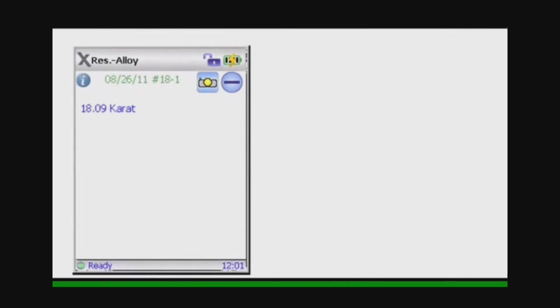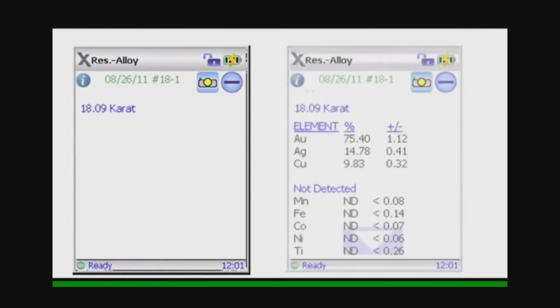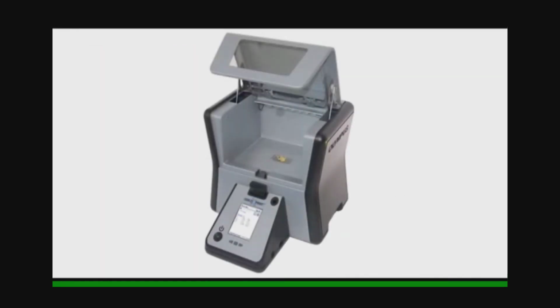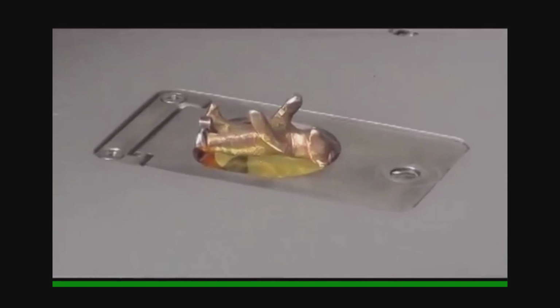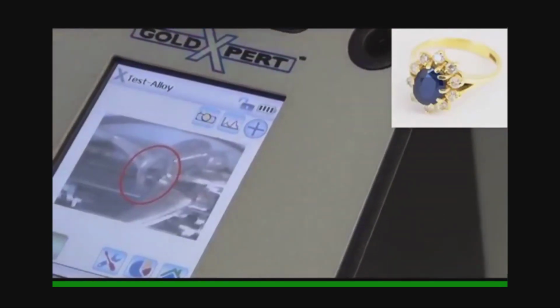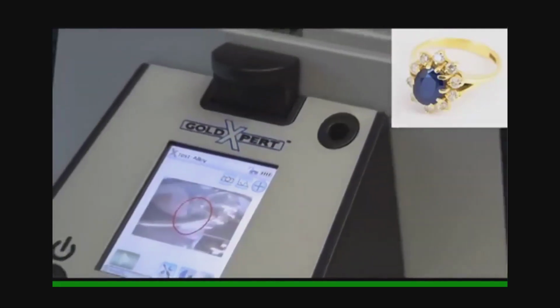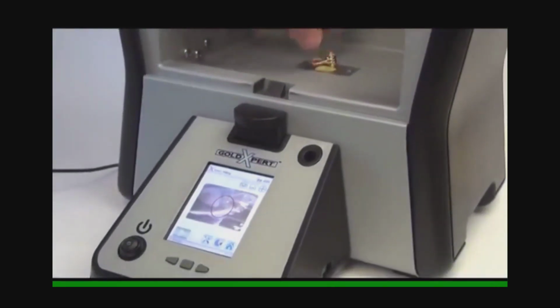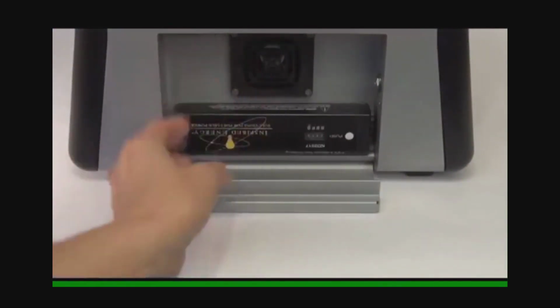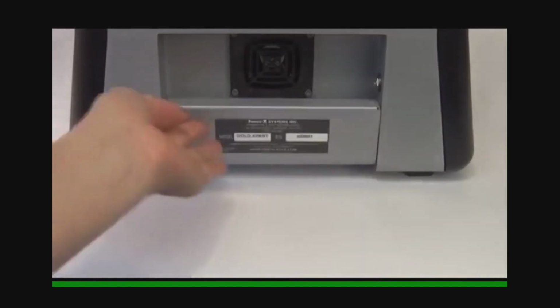The Gold Expert's viewing window and well-lit chamber allow both operator and customer to see the sample as it is being analyzed. Carat mode, or the more comprehensive chemistry analysis mode, can be selected. The Gold Expert uses X-ray fluorescence, a non-destructive and fast analytical method, to test samples. It's easy to use and adapts to nearly any sample size or shape. An integrated camera allows the Gold Expert to focus on and get results from individual components. This is useful when testing pieces that include gemstones.